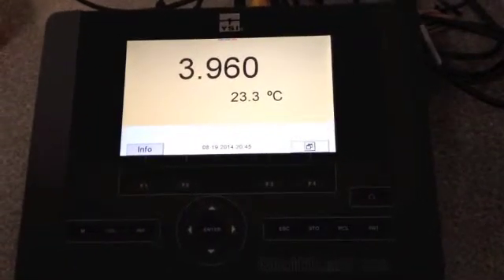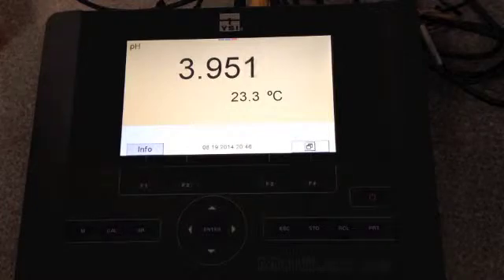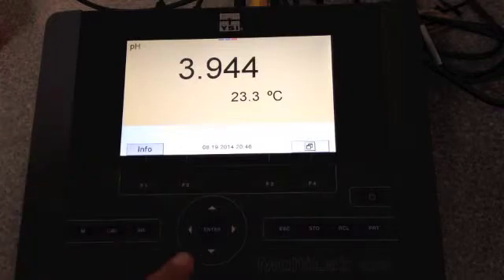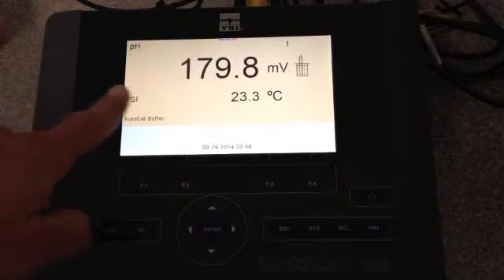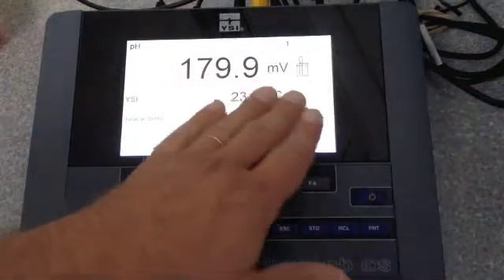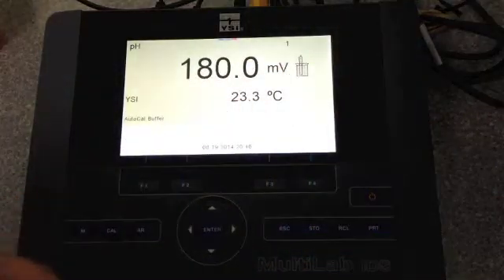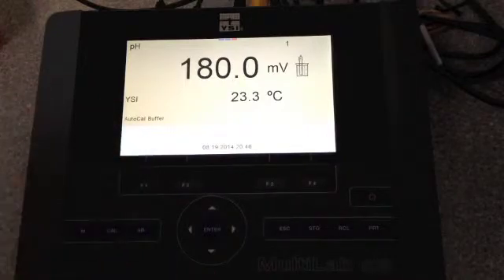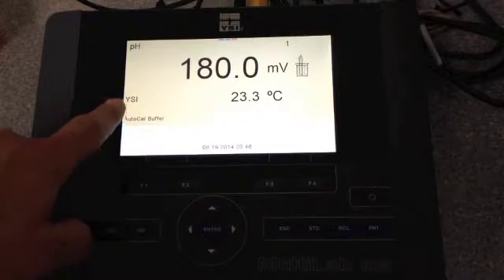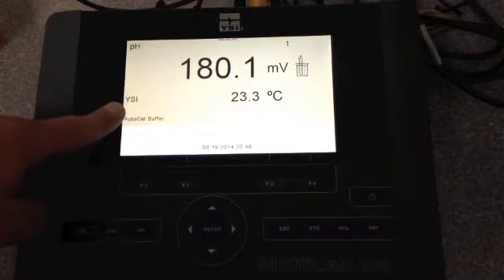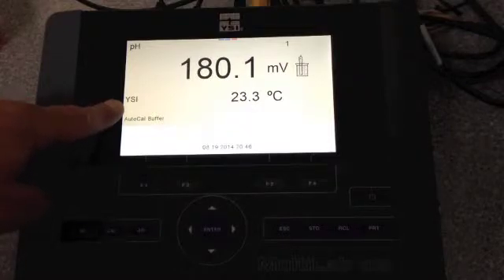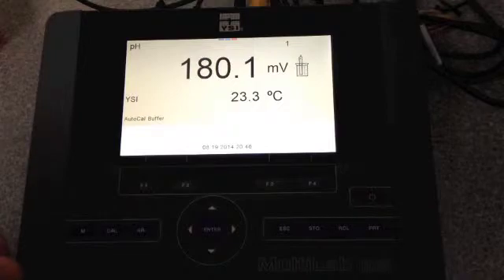I'm going to walk you through how to do the calibration procedure. I'm not so much going to focus on how to do the solutions and the rinsing and all that. I just want to focus on what's going on on the meter itself. Once we're in pH mode, we're going to hit the cal button off on the left, and as you can see, it changes to the millivolt mode. You don't have to pay attention to that, but that's the actual language that the meter and the probe speak. And just take note that it shows that we're using the YSI buffer set, and it's set for auto cal, which means it'll calibrate itself.